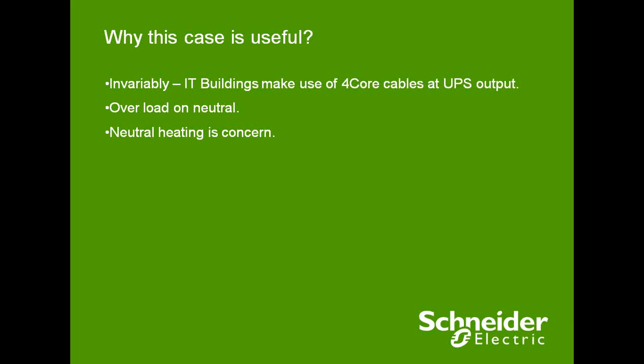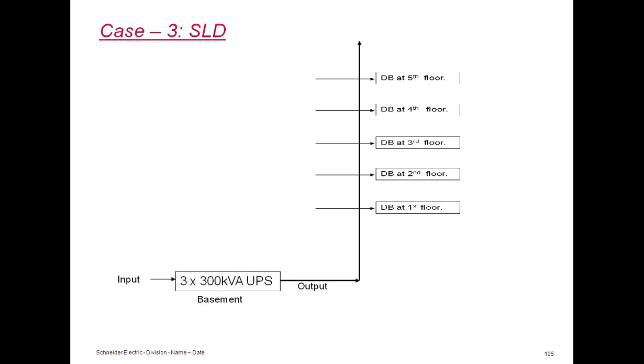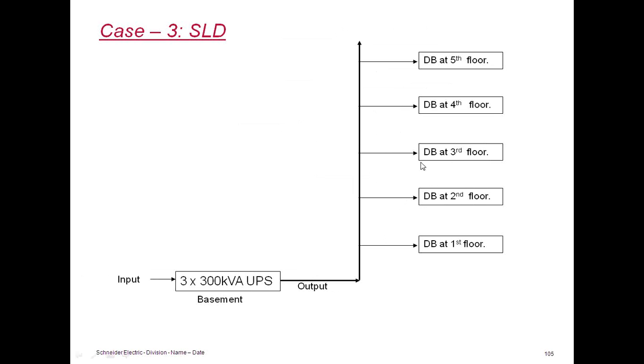Yeah. So this is a schematic of this IT building. It's a building having 5 floors, 1, 2, 3, 4, and 5, and a basement. In the basement, they had 300 kVA UPS, 3 numbers in parallel operation, and the output is going out through a cable. We have rising mains from the basement up to the top floor, the 5th floor, and we have distribution at each floor. We have cable tappings from the main rising mains going to our distribution boards. Our distribution board is feeding computers, servers, all IT loads in the system.